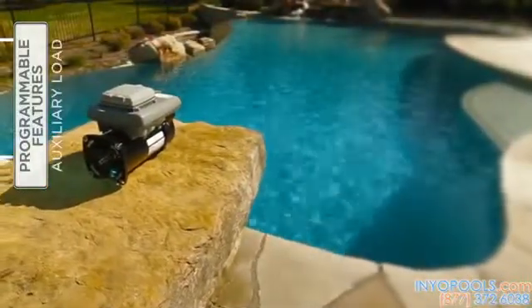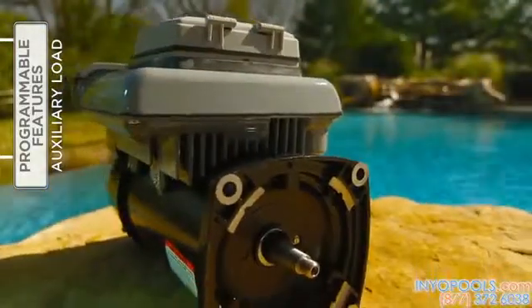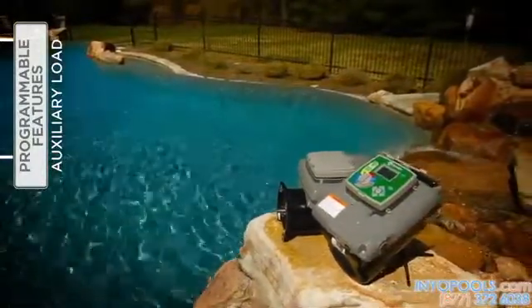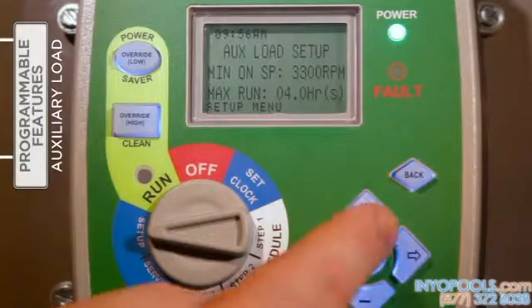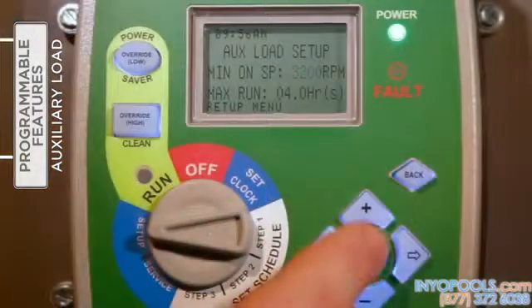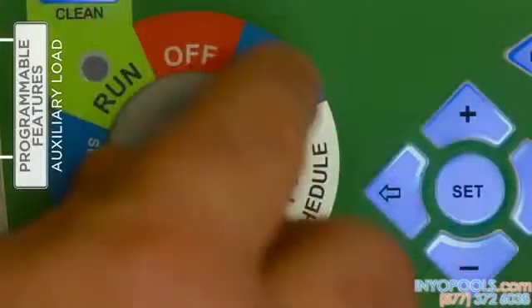The auxiliary load relay inside the V-Green control is designed to provide AC/DC power to a load that should not be energized without adequate water flow from the pump, such as a pool heater, booster pump, or saltwater chlorinator. With the selector knob on 'Setup,' press the right arrow button to access the auxiliary load feature, then press 'Set' to enter change mode. Press plus or minus to increase or decrease the minimum speed, then press the right arrow to move to the maximum run time field and use plus or minus to affect changes.